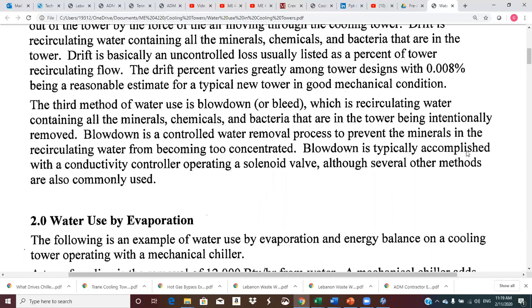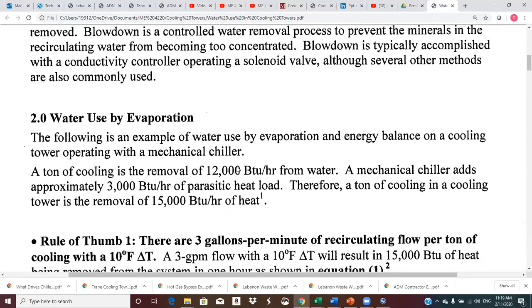This is often done automatically with a conductivity sensor. So we measure the electrical conductivity of the water. That's a surrogate for the mineral content. And then that can automatically control a valve, which will open and close to maintain a certain conductivity setting. And there are other ways to do it as well.